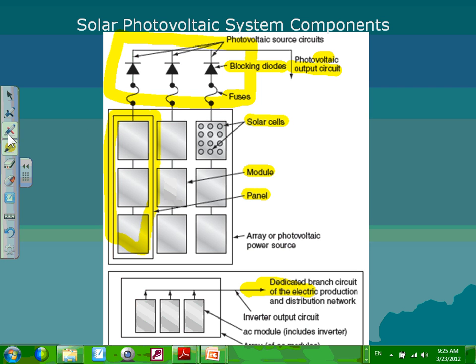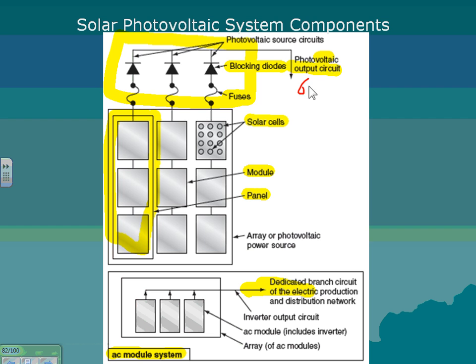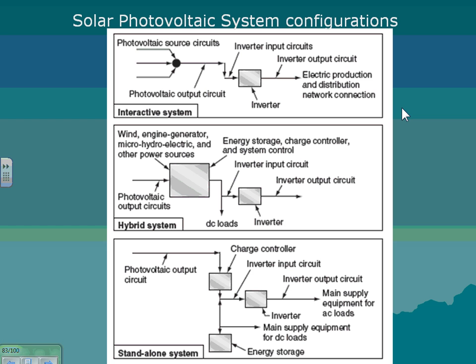Versus what you're getting down here, which is DC. So right out of this output here, I could have up to 600 volt DC, just for the sake of argument, and I'm capturing 50 amps out of this system. And these are all DC. Do your math: you multiply 50 by 600 volt, that will give you how much power you have in the system. That will get you the kW or kVA. So this is really the bottom line. I'll show you a couple of things, how the system works. The top one is a DC, the most common one is the DC. The bottom one is the AC, where the inverter comes with the panel. Here's how they do them. You're going to see the same terminology that we just talked about with the wind. They use interactive system, they use hybrid system and standalone system. They added the word hybrid here.